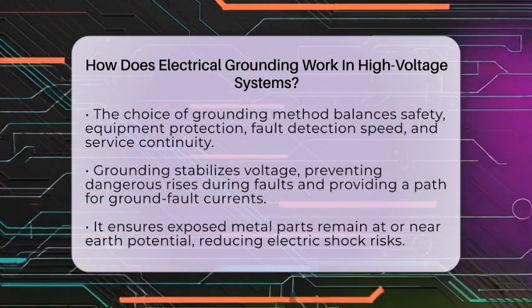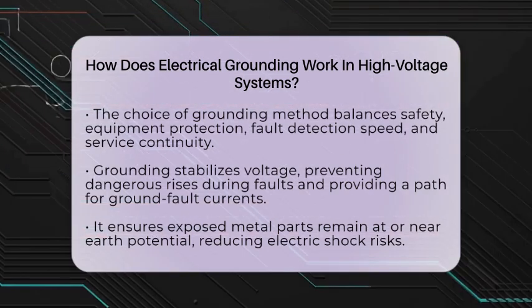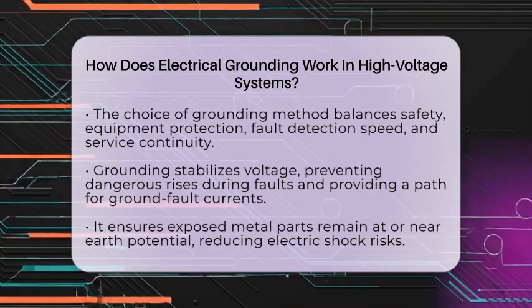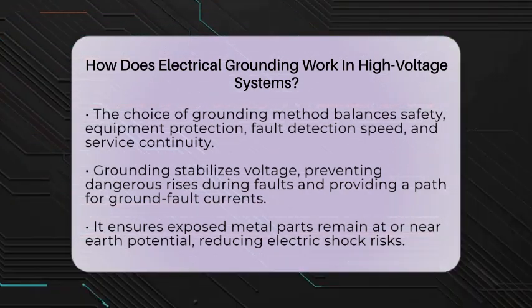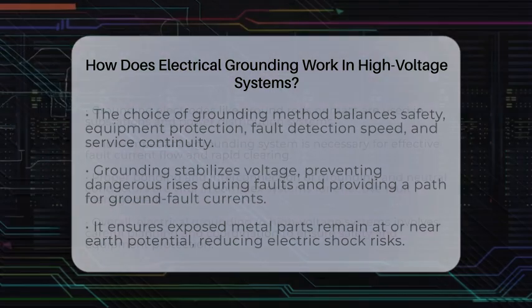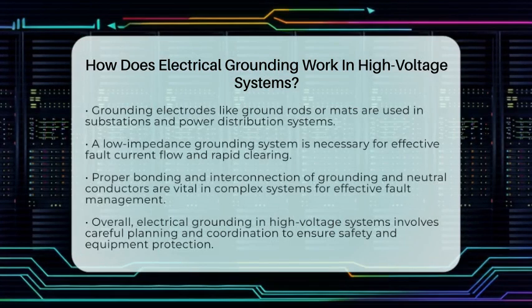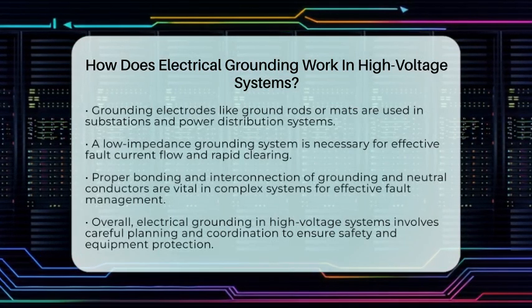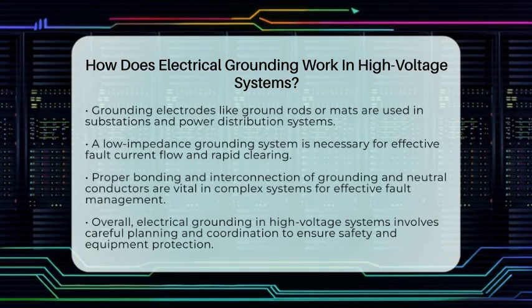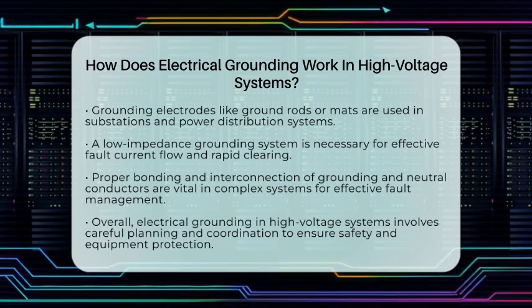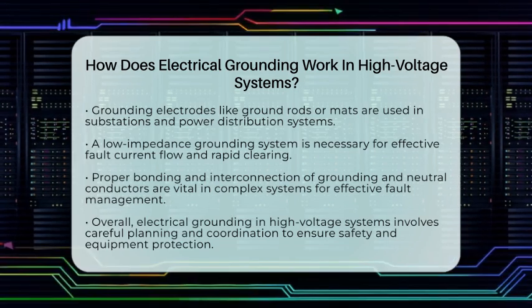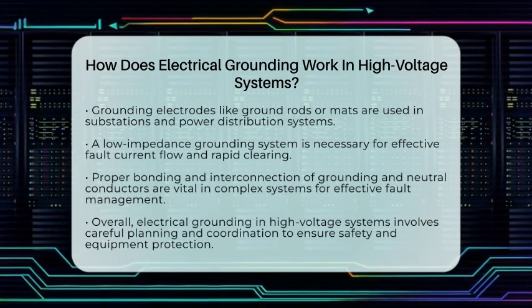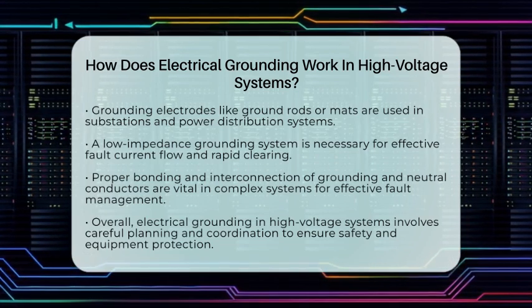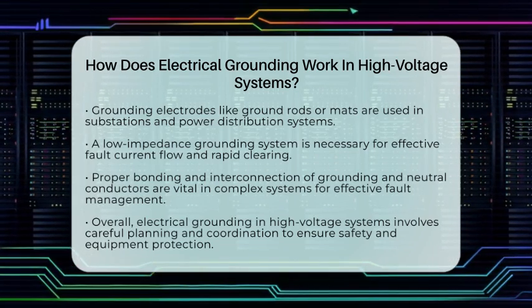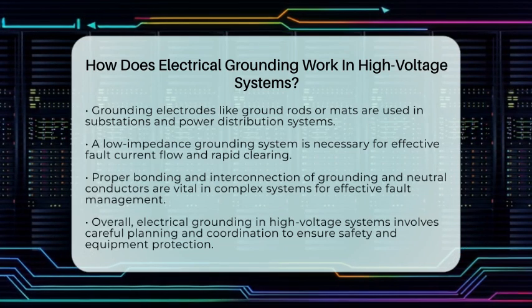For personnel safety, grounding ensures that exposed metal parts of equipment remain at or near earth potential. This reduces the risk of electric shock, which is vital in high-voltage environments. In high-voltage substations and power distribution systems, grounding is implemented through grounding electrodes, such as ground rods or mats. These are connected to the system neutral and equipment frames.